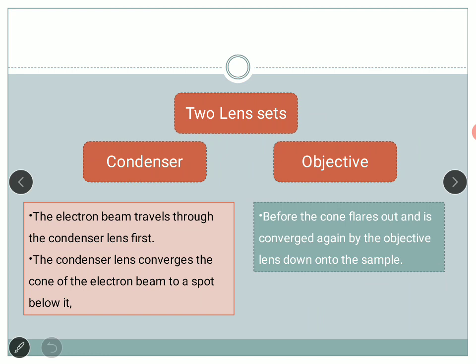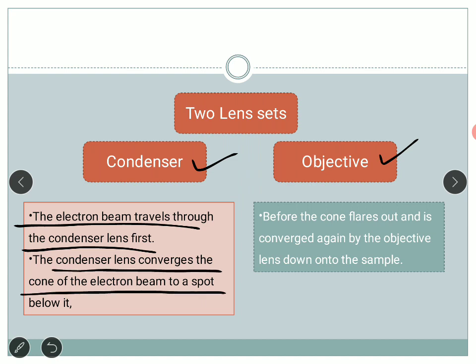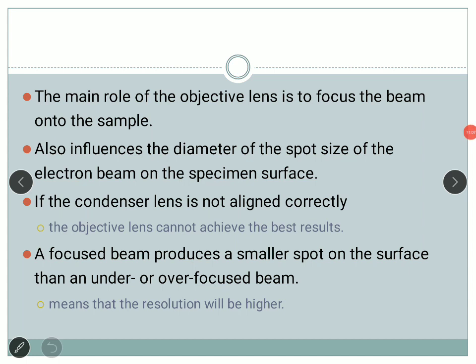There are two lens sets: the condenser lens and the objective lens, each with a specific purpose. The electron beam travels through the condenser lens first, which converges the cone of the electron beam to a spot below it. The objective lens then re-converges the beam — before the cone flares out again — down onto the sample. The main role of the objective lens is to focus the beam onto the sample.